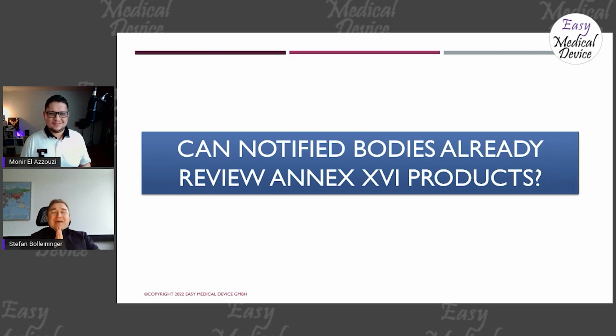Good point. Actually, if you approach the notified body and say, hey, we have an Annex 16 device, they run away as fast as they can move, because until that regulation is applied correctly, they're out of business on that end. And they won't tell you, because there's no clear idea. So my perspective is still: walk to your competent authority and approach them with your idea. Sometimes it helps a lot to give them your intent, how you feel.